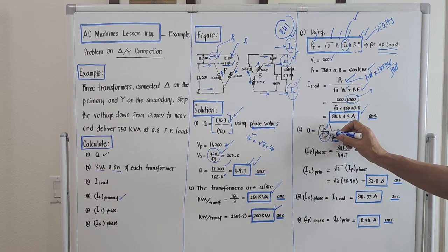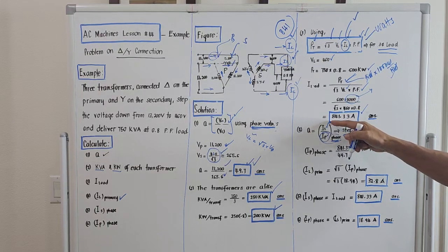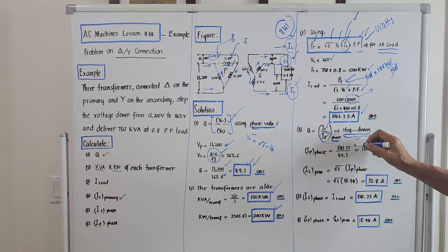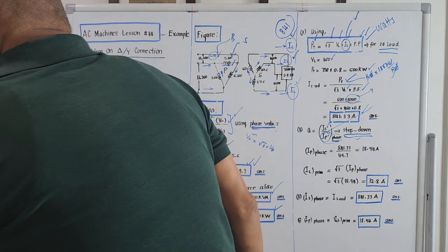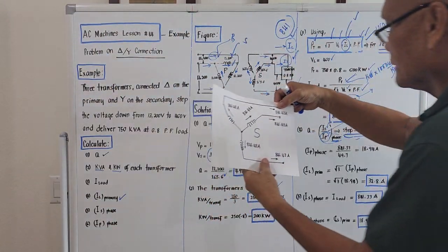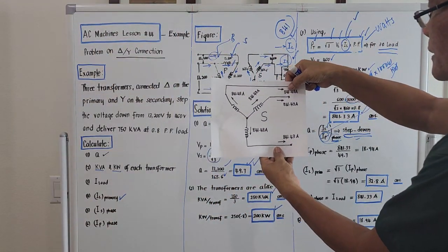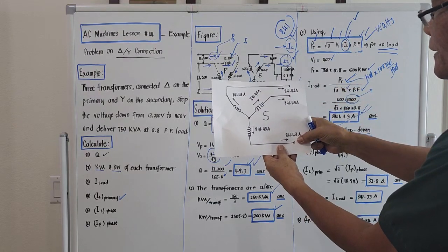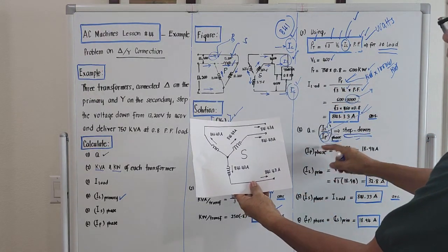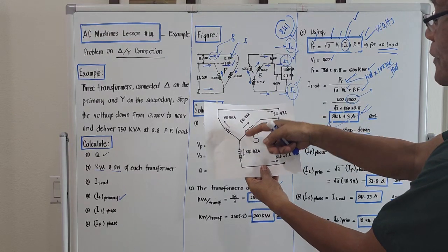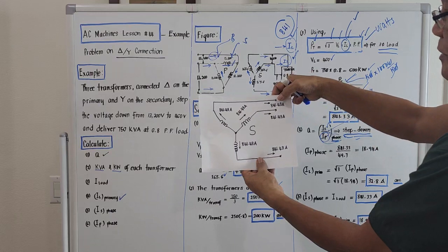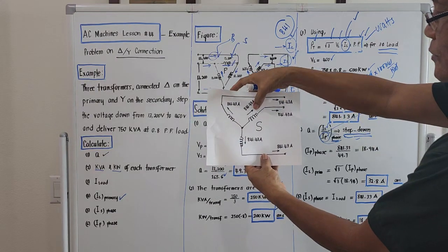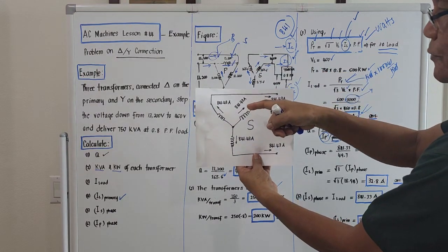If we compute for this, it will be I_S over a. So we computed I_S over a. I_S is actually this one. The line currents are actually 841.33. And the secondary current being mentioned here is the current coming out from the windings. But since the connection is just series, this is 841, so the secondary current should also be 841.33 amperes.